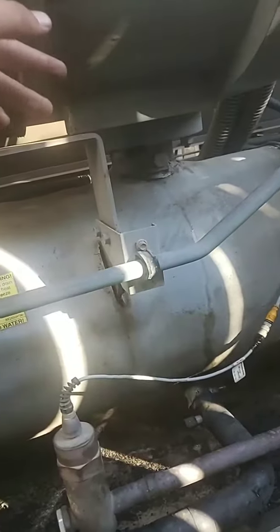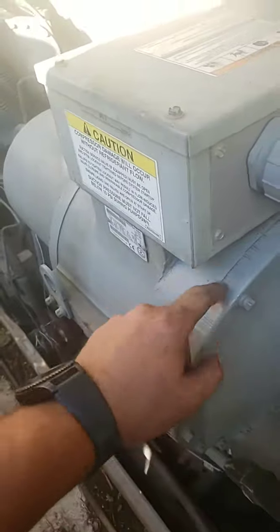This particular compressor has a number of leaks on it. It's got leaks on these seals here on the discharge side of the circuit. Like this is the actual muffler assembly. All of this has several leaks. A compressor on the other side had a leak on this seal. I fixed that earlier this week. So this particular system has several issues. We're just waiting on the customer to say, yeah, go ahead, let's fix it.